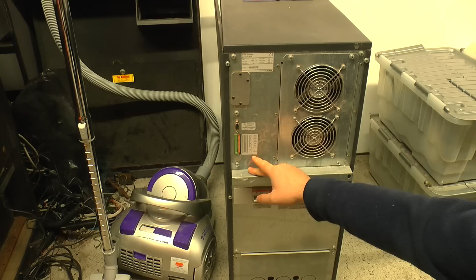There's a bypass fuse as well, so if you're running the system in economy mode, so it's sitting alongside as a line interactive UPS rather than online, then there's a fuse there. And there's obviously these ones as well for the rectifiers. There's a maintenance bypass breaker, which would normally be off, and there's the input fuse. Sorry, that's the output isolator there.